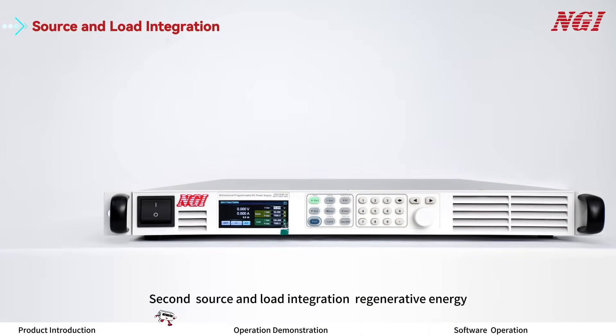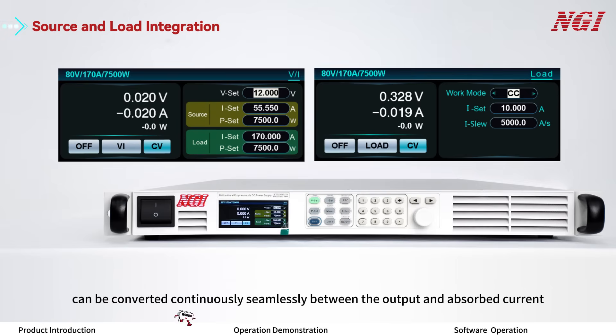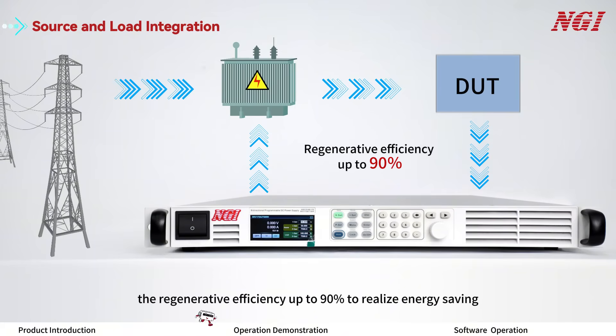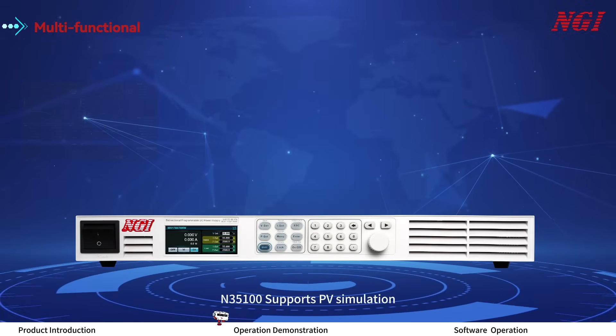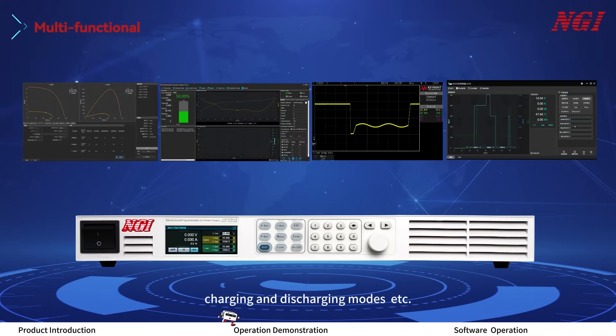Second, source and load integration with regenerative energy: with the integration of power supply and regenerative load, the N35100 series bidirectional power supply can be converted continuously and seamlessly between output and absorb current. It can not only provide external power but also absorb power and return electric energy to the grid cleanly, with regenerative efficiency up to 90%, realizing energy saving. Third, multi-functional rich application scenarios: the N35100 supports PV simulation, battery simulation, car waveform, charging and discharging modes, and more.